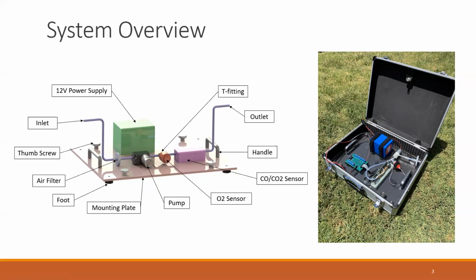Air comes through our inlet hose and then goes to an air filter, which filters out the soot particles. Then we have our pump, which pumps the flow through, then it goes through our measuring devices, the O2 and CO2 sensors, and then out our outlet, which goes back up to the exhaust pipe.